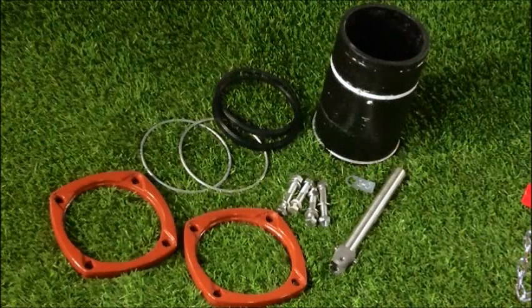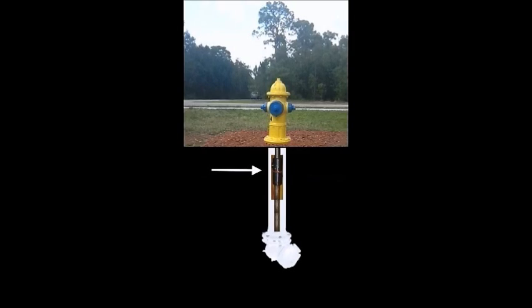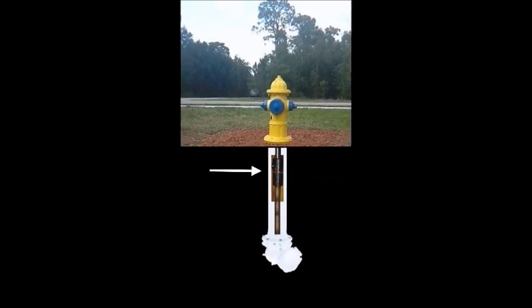Often times, when extensions are used to raise a hydrant to grade, the internal connection remains below grade, which might cause a malfunction to the break flange feature.